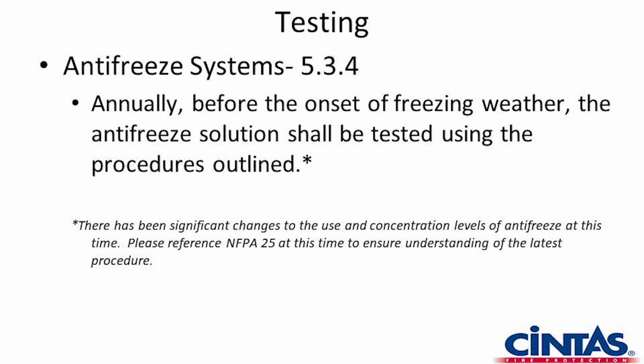All that said is we're supposed to test. We want to test right before it gets cold. Make sure that any area that's being protected by an antifreeze system, we take a small sample of the water. We test it with a refractometer. We're testing for specific gravity to determine what the freeze point of the solution is. And in NFPA 25 in the annex, back in the back of the book, there's a chart of the United States with contour lines, much like you would see on a topographical drawing of land, but it shows the line moving through the United States, and it will be tagged with the freezing temperature.